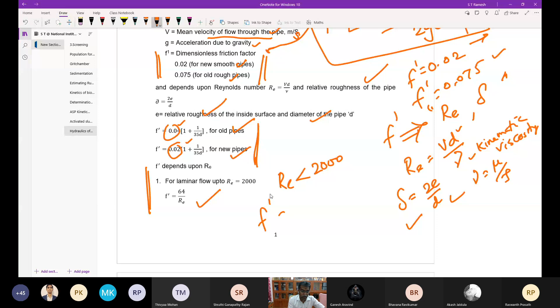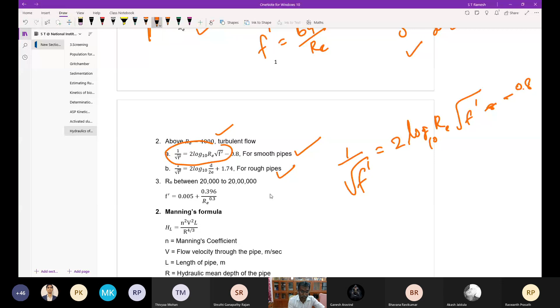If the Reynolds number RE is less than or equal to 2000, you can use this formula directly: F dash is equal to 64 by RE. Above 4000, it may lead to turbulent flow condition, and for a smooth pipe you can use this formula, that is 1 by square root of F dash is equal to 2 logarithm of 10 RE square root of F dash minus 0.8. For a rough pipe you can use this formula, and if it is in between 20,000 to 20 lakhs, you can use this formula to calculate the F dash value. Is it okay?